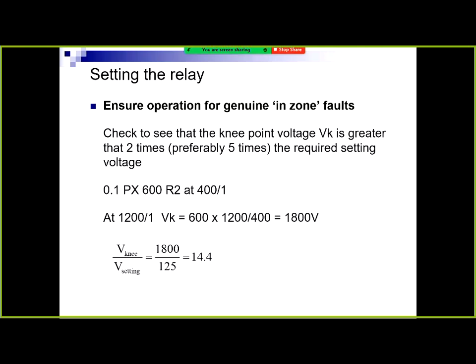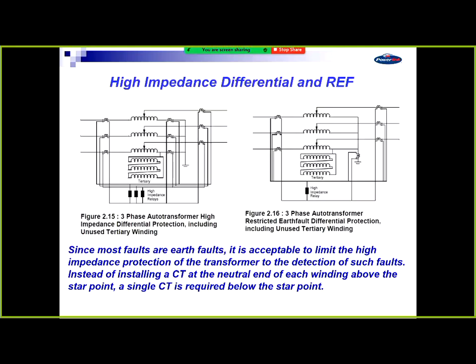What you also need to do with these is to check that the knee point voltage is at least 2 times your setting and preferably 5 times. That's another thing for PX class CTs. You've got your knee point voltage there. It is at 1200 to 1, it's the ratio of 1200 to 400, 3 times 600, which is the 400 to 1 knee point voltage, 1800 volts. 1800 divided by 125 is 14.4. We're over 5 times, so we don't need to worry. So we tick that box. The CT is okay.